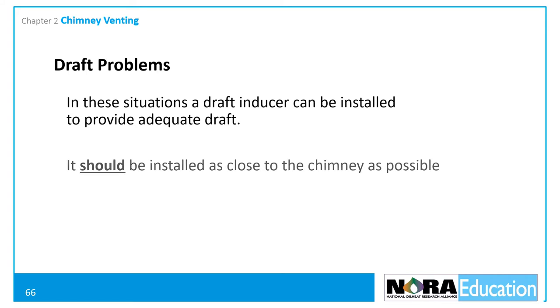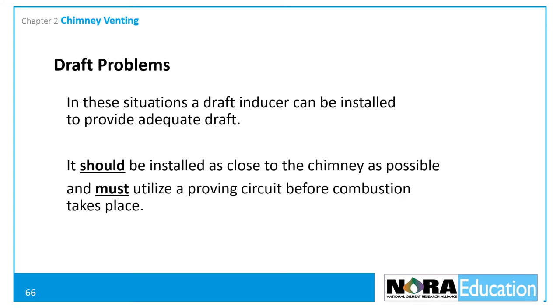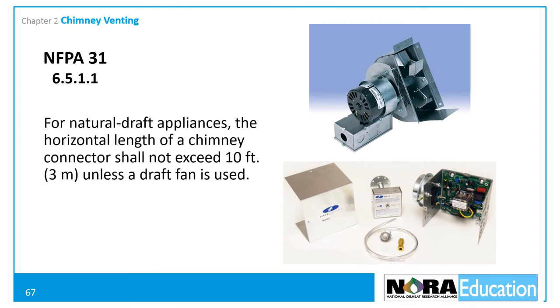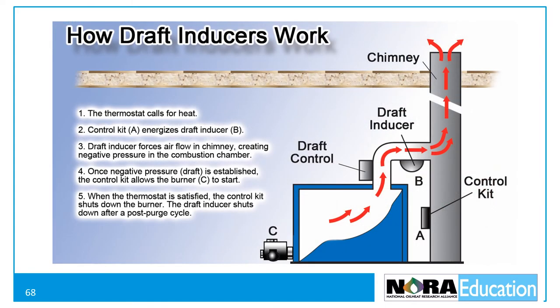The draft fan should be installed as close to the chimney as practical and must be electrically interlocked with the appliance utilizing a proving circuit before combustion takes place. NFPA 31 requires a draft fan when the horizontal length of the chimney connector is longer than 10 feet. On a call for heat, the control kit energizes the draft inducer, which forces airflow in the chimney, creating negative pressure in the flue pipe, heat exchanger, and combustion chamber. Once negative pressure is established, the control kit allows the burner to start. When the call for heat is satisfied, the control kit shuts down the burner, and the draft inducer shuts down after a post-purge cycle.